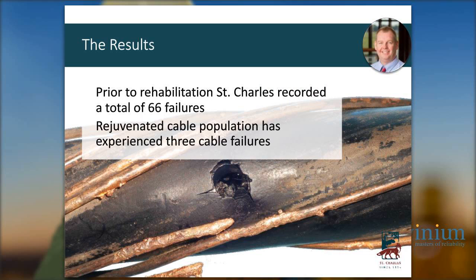Of the 3 that failed, all were very early after cable injection—one within a week, the others within 3 to 6 months. Those are indicators for us that we're exactly where we need to be: we injected it maybe 3 or 6 months late, and had we been just 3 or 6 months earlier, we probably would have avoided that fault. But it gives us confidence that we're not injecting subdivisions well before they need it. At this point, we feel we're right at the cusp—injecting cables that are going to fail within the next year.